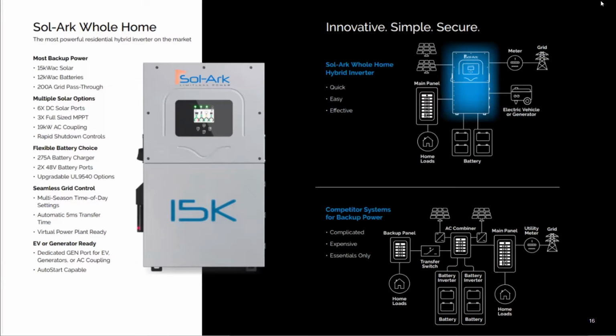So the generator port on the Sol-Ark is throttled to 19 kilowatts, but you can land a 22 or 24 kilowatt generator on that. You can also land a generator on the grid side using an external transfer switch. I would strongly recommend going through the Sol-Ark training portal when designing with generators, because they are tricky.